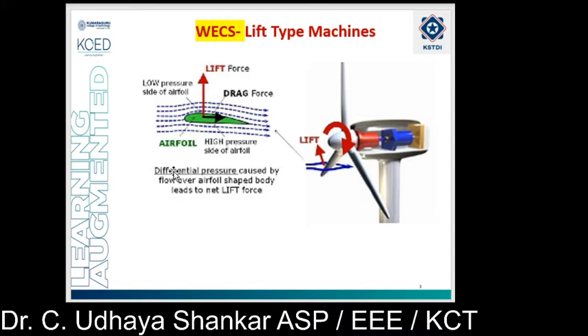Lift devices are more efficient and turn faster than wind. They are able to benefit from high power densities available in strong winds. The ratio of power extracted from the wind by a lift device to that of a drag device is usually greater — it will be in the order of 3 to 1 for the same area construction. Lift type rotors are often tapered or twisted to reduce bending stresses and to improve stalling performance. Each type of rotor has its own tip speed ratio, and by changing the turbine speed proportionately with respect to wind speed, we can maintain a constant tip speed ratio.